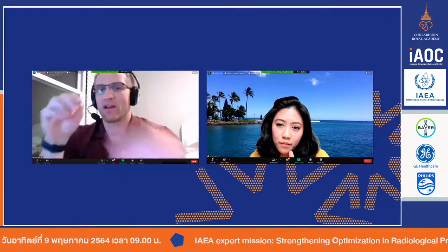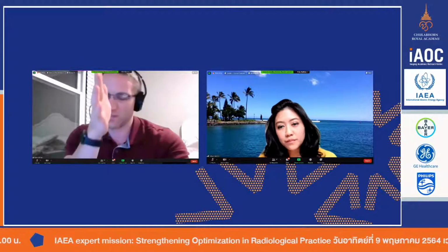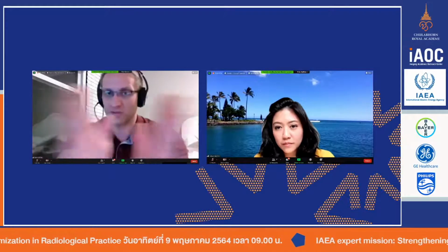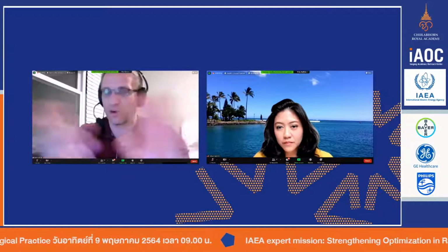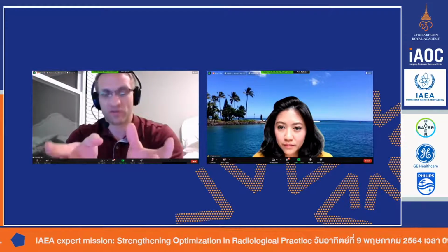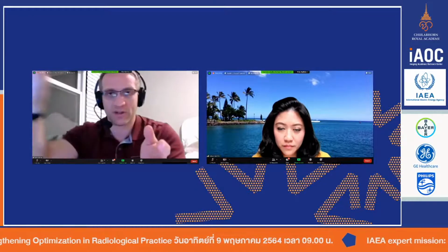And the one thing I would say to all of that is, remember that it's not ever based on one patient. And so that's why we collect all of these. So if a patient specifically was imaged and they're lower than or above, as an example, the 2 standard deviation DI, you as a hospital have to decide if you're comfortable with 2 standard deviations or only 1 or something in between. Let's assume 2 for now. If the value falls outside of that, in that moment, you make sure the images are sufficient for the radiologist. If they are, the patient goes away, the radiologist does their read and they write their report, or they dictate their report. And then that patient gets listed and gets put in a bucket that we will review.